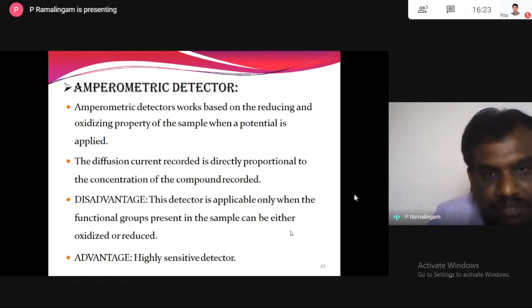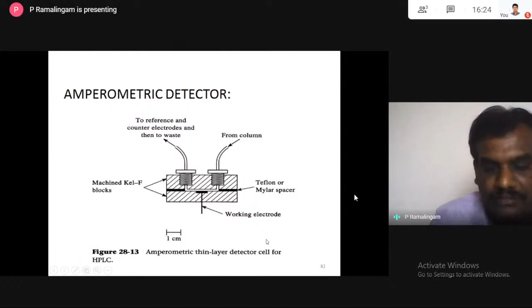From the column, the eluent comes here, and there is a Teflon or Mylar spacer here, and a working electrode. After that, detection takes place. Here the sample undergoes electro-oxidation or reduction at the working electrode. It detects the diffusion current, with a reference and counter electrode. Based on the reference electrode and working electrode, the diffusion current is measured from here.